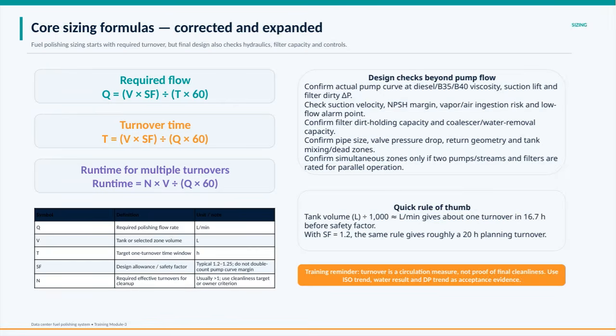Let's dive into the core sizing formulas for fuel polishing systems. The process begins with determining the required turnover, which is essentially how often the entire volume of fuel should be circulated through the system. The key formula for required flow rate is Q equals volume times safety factor divided by turnover time in minutes. This tells us the flow rate needed to achieve that turnover within the desired time frame. Turnover time itself is calculated by rearranging this formula. It's the volume times safety factor divided by the flow rate, again converted into hours.